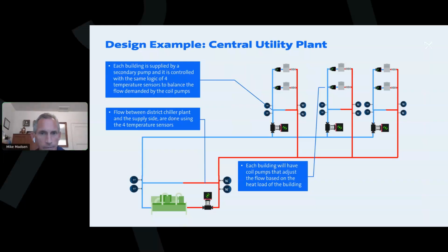Okay, so here's one. You were showing that it was like, I don't know, 50 kilowatts to start, and after you were done, it was 15. But was that 50 and 15 kilowatts total pumping of the smaller pumps and the new primary pump, or was that just the primary? It was total, primary and secondaries. So these air handlers are having pumps on them that are what, fractional horsepower? Is that what you're thinking? Half horse, third horse, three-quarter horsepower. Okay, that makes sense.